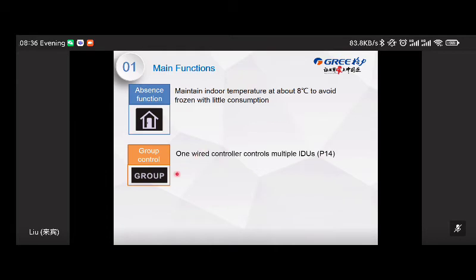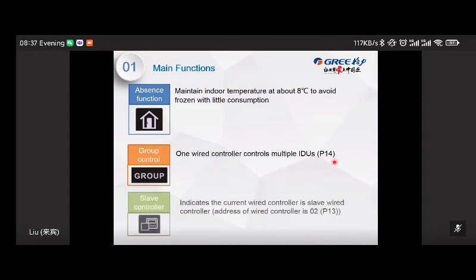And this icon is the group. If you use the wired controller to control multiple indoor units, then you need to set the actual quantity for that controller, how many indoor units you want to control with one wired controller. And this is the code P14. You can operate the wired controller to set this code and set the value. If not, it may cause some error display and some malfunction. And this one is the slave controller.